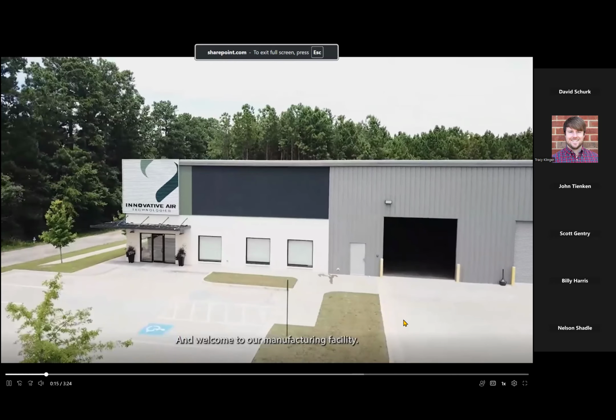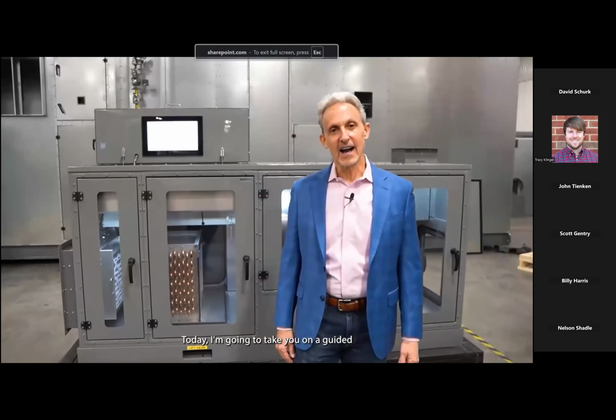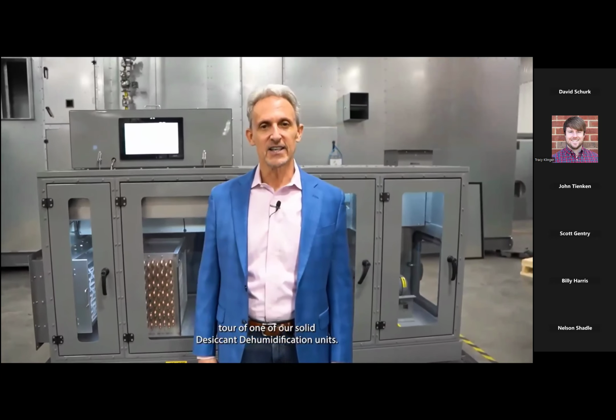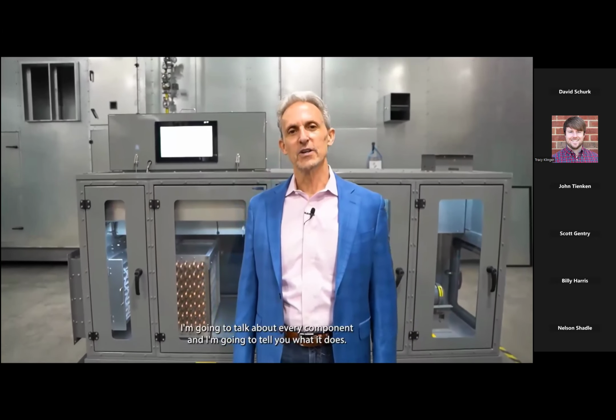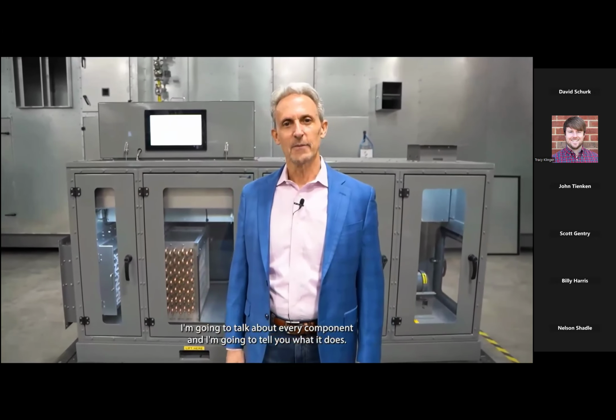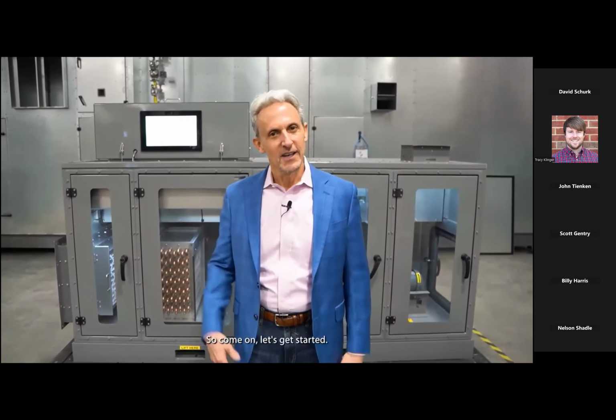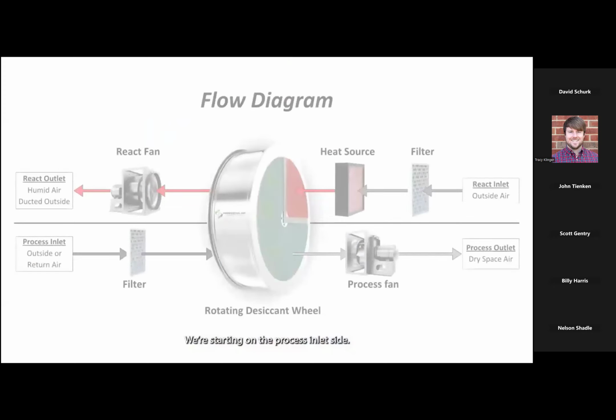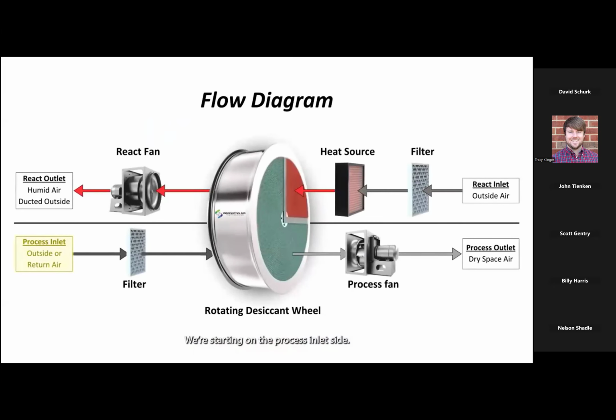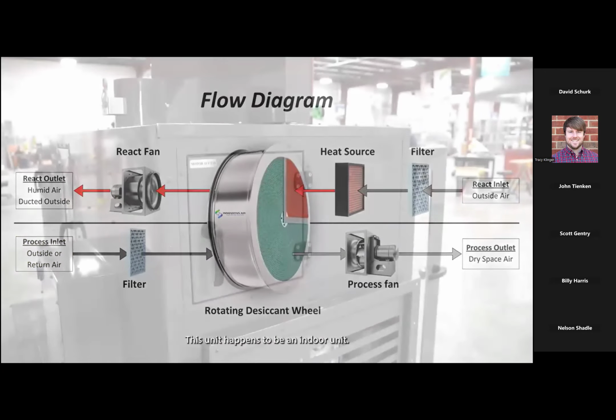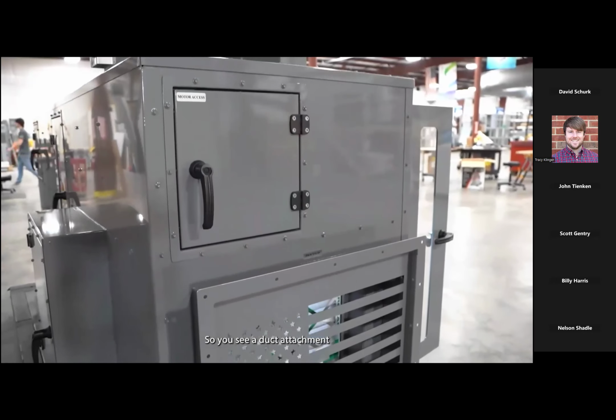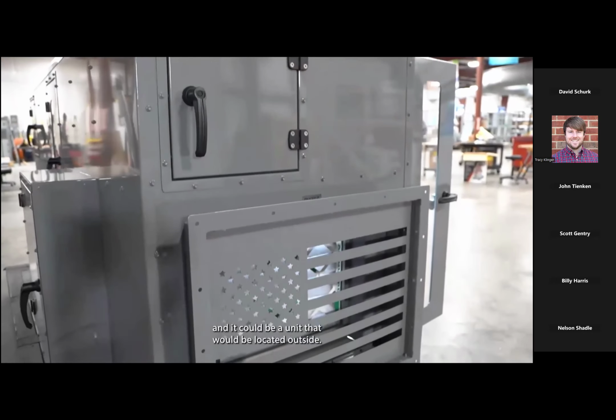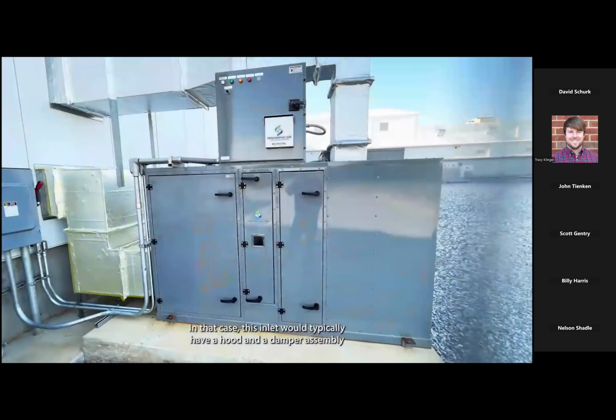Welcome to our manufacturing facility. Today I'm going to take you on a guided tour of one of our solid desiccant dehumidification units. I'm going to start on its inlet, work my way through its outlet, talk about every component, and tell you what it does. So come on, let's get started. We're starting on the process inlet side. This unit happens to be an indoor unit, so you see a duct attachment, and it could be a unit that would be located outside. In that case, this inlet would typically have a hood and a damper assembly.